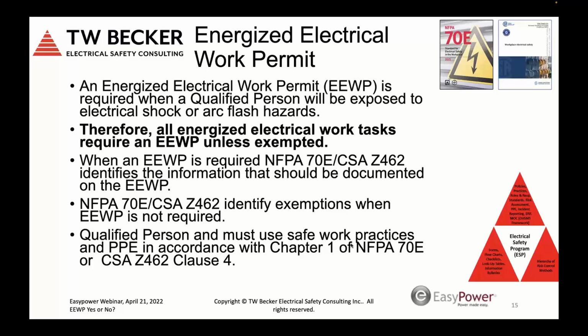The permit, like I said, is a separate policy or a separate document that's a permission type document. And we do look to 70E and Z462 because it's the only place that this energized electrical work permit shows up in relationship to energized electrical work. So this permit, if you interpret it, a qualified person would need it for any work task they perform where they're exposed to arc flash and shock hazards. And wow, we'd have lots of permits being issued often if that was the case, right?